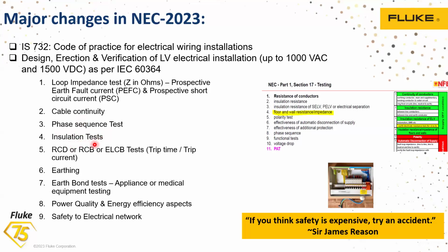Regularly check the insulation tests, depending upon the size of the equipment, and within the facility on the low voltage side, 1 kV is definitely the one to use. Then check the RCD, ELCB or RCCBO, to check the tripping time and tripping current. Ultimately we are talking about the functionality of the RCDs which are installed for safety purposes, right? So we are going to test that.